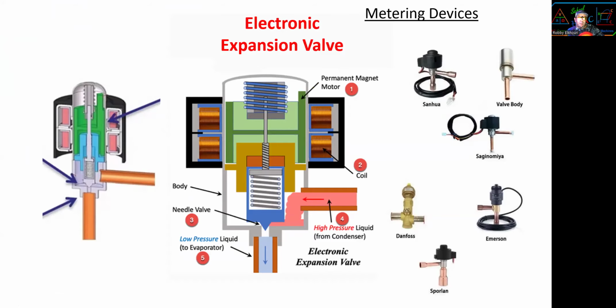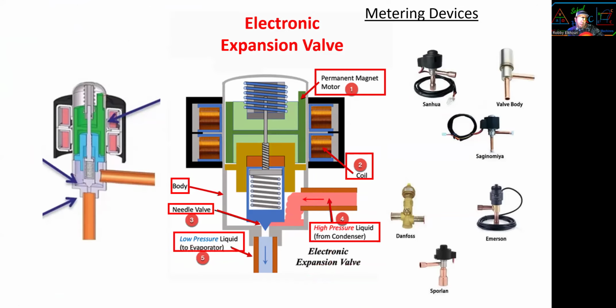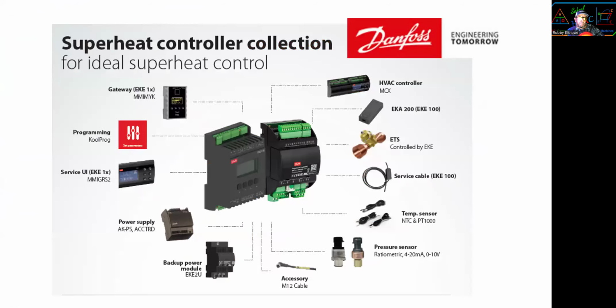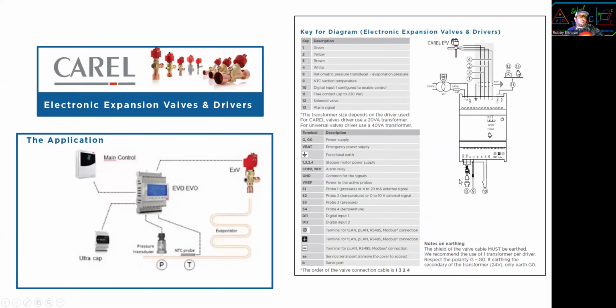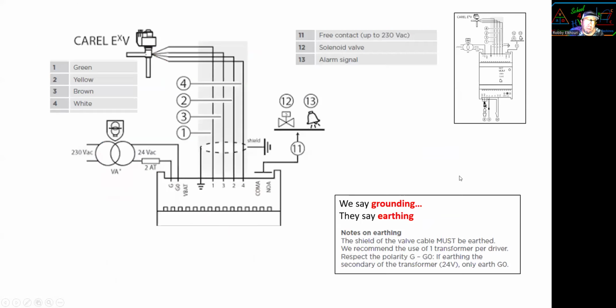Now this is the expansion valve. We have the motor section. We have the body and needle valve. And we have pressure in and out, high pressure, low pressure. And separate, another example, the motor, the valve. This is an example of so many different kinds of valves. I mean, so many options we can put into it. Backup power, computerized. It's called a superheat controller. All right, now this is what I found online, electronic expansion valves.